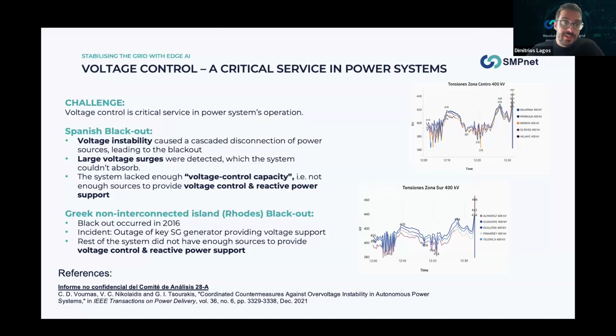We have the very recent incident of the Spanish blackout, where, based on the reports that have come out, voltage instability has been identified as the core reason that led to this cascaded disconnection of power sources that led to the blackout. On the right, I have some graphs of voltage measurements recorded in the system, and we see that there were some large voltage surges detected that the system couldn't absorb. And what we mean by couldn't absorb is that the system was lacking enough voltage control capacity. That means that there weren't enough sources available to perform the voltage control by providing reactive power support.